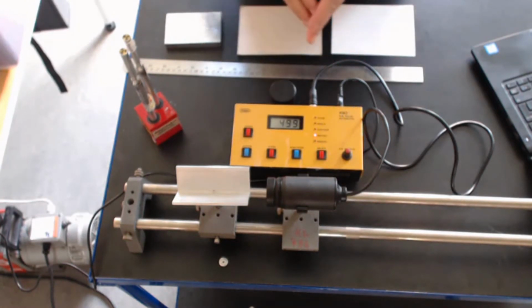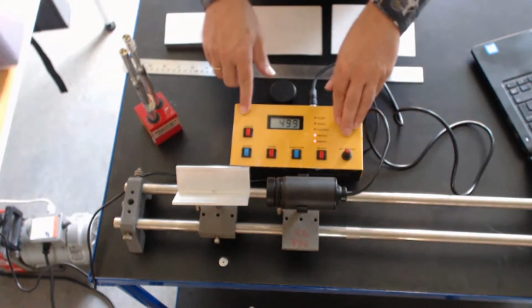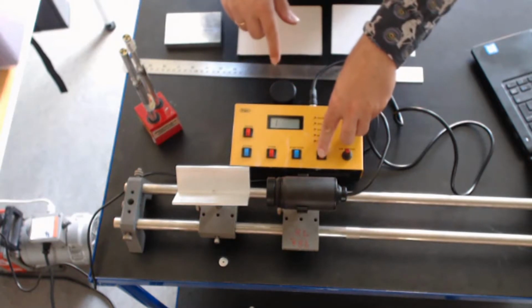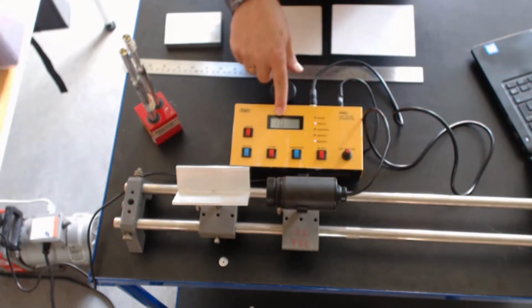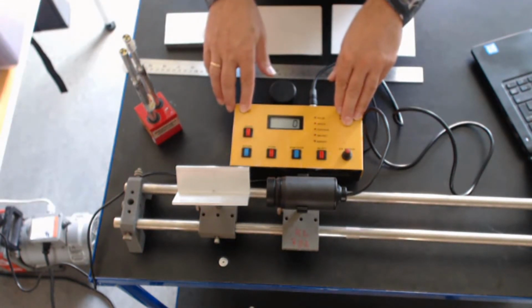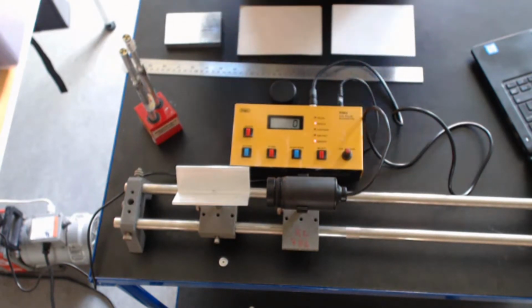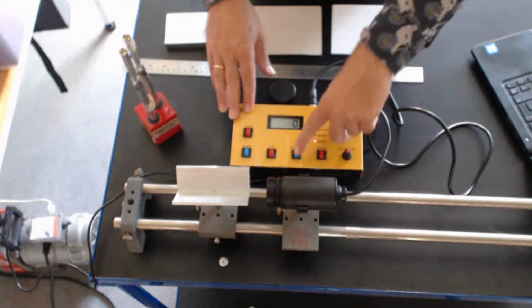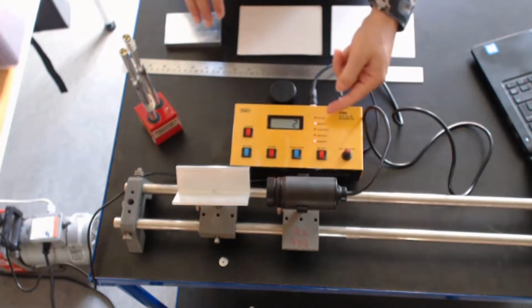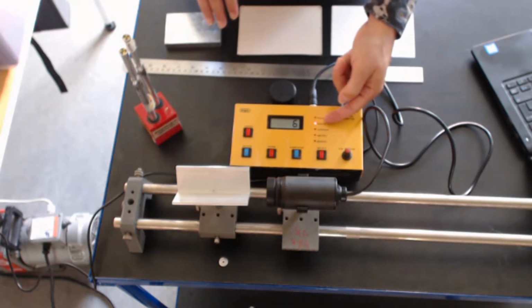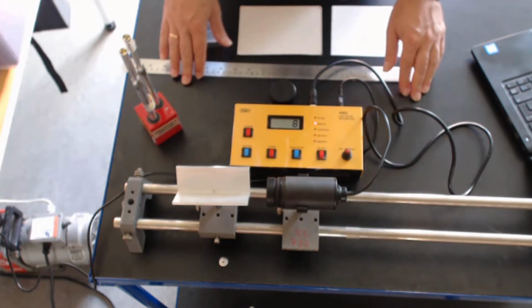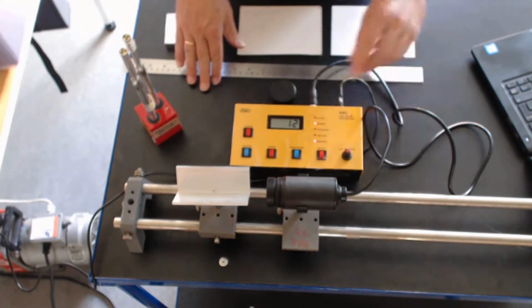So right now I have switched off the sound, so it's not too disturbing, but we'll start that soon. Now let's switch to count for a period of 10 seconds each time, and I switch on the sound now. Now we hear the first one, and then if I press start, we will collect the background counts for like 10 seconds. Let's see, and when this is ready, it will start blinking. How many background counts do we have? 12 counts in 10 seconds.